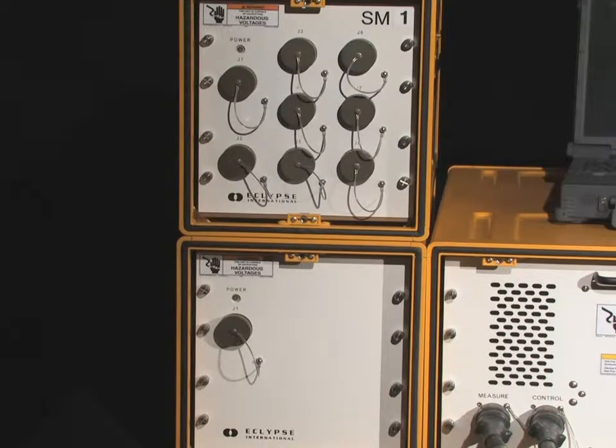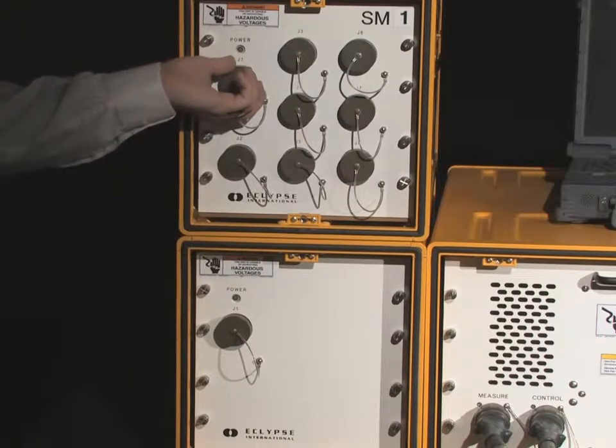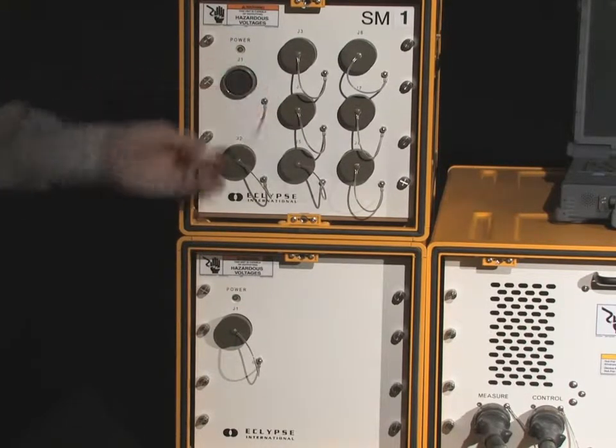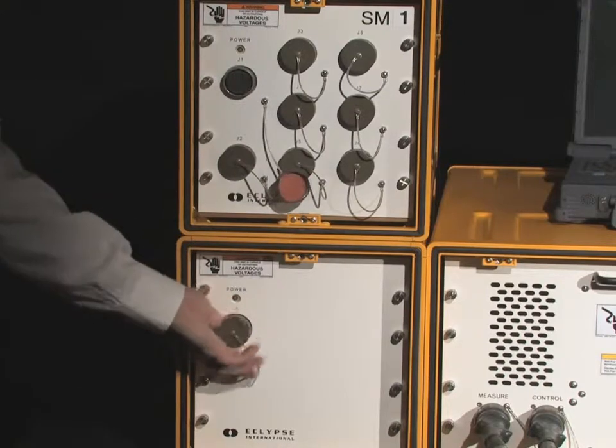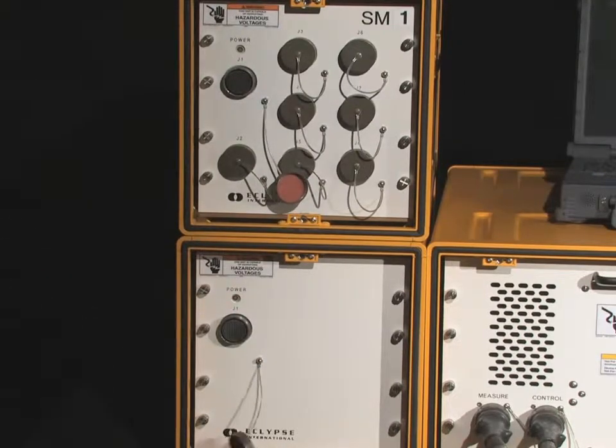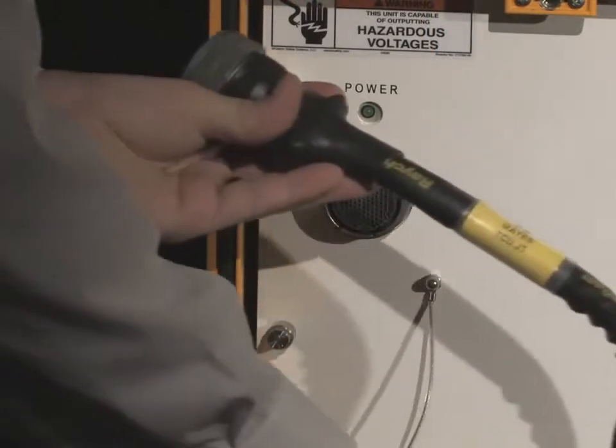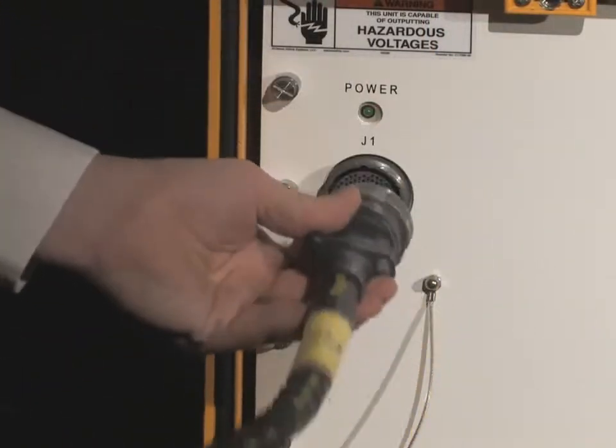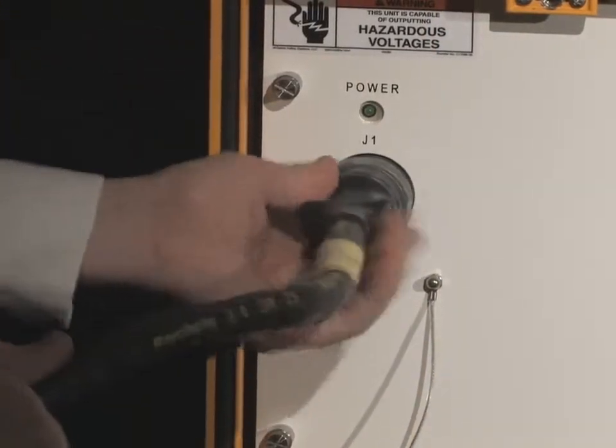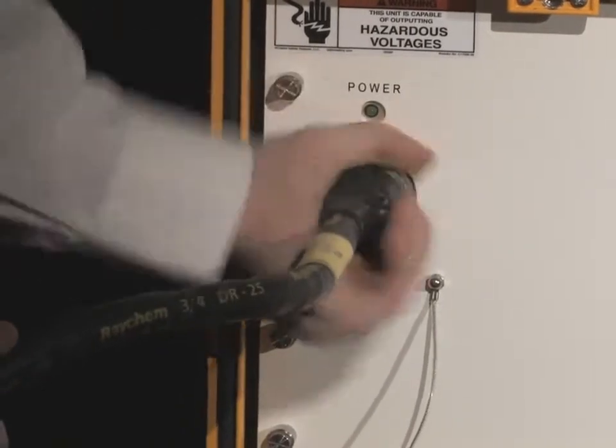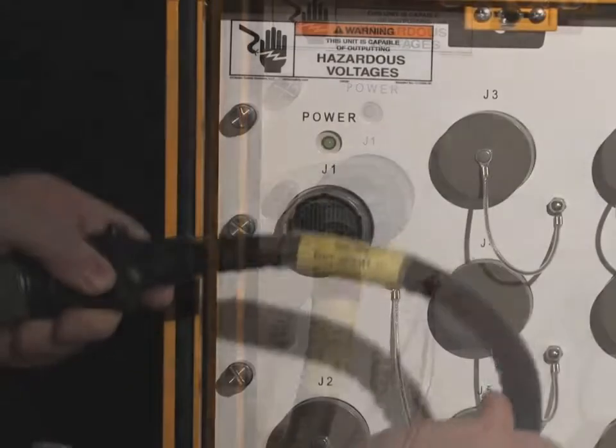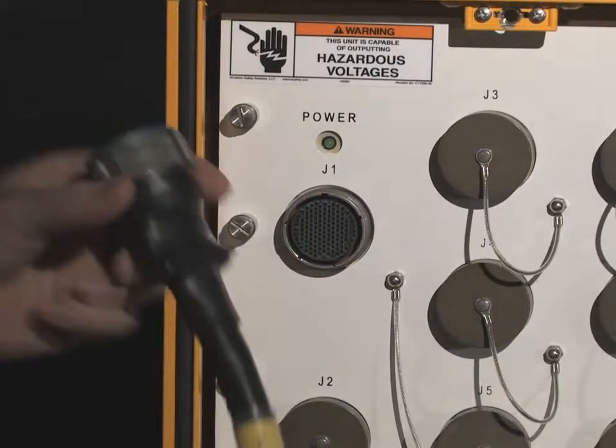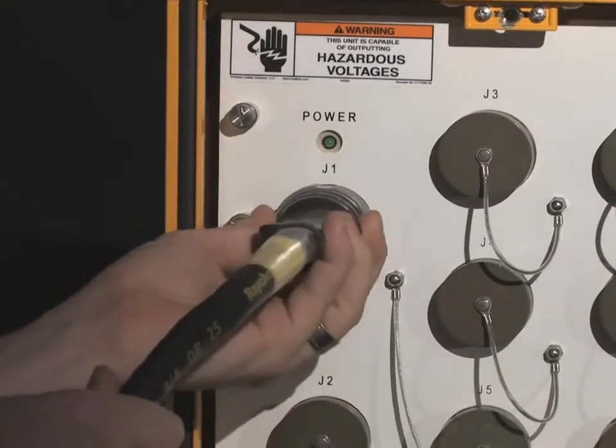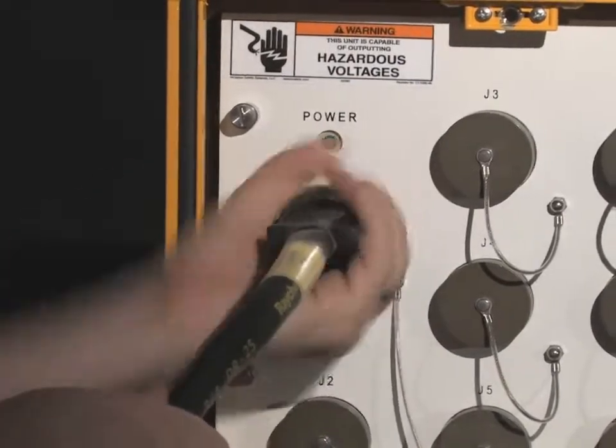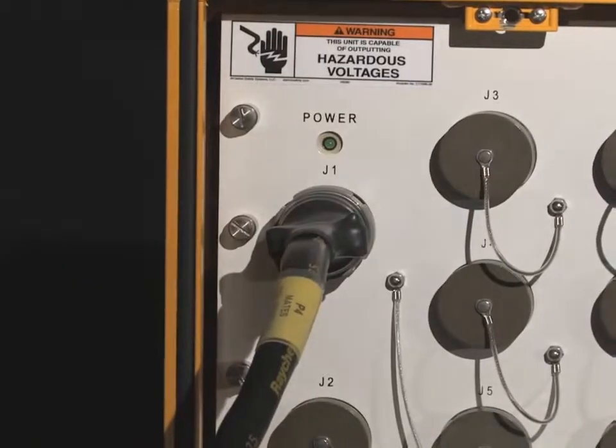On 500-volt systems, locate the J1 connector on the front panel of the switch module unit and the J1 connector on the front panel of the test control unit and unfasten the dust caps. Connect the P3 test control unit J1 and P4 switch module J1 ends of the external load module interface cable to J1 on the test control unit and J1 on the switch module. Let's go over that one more time.